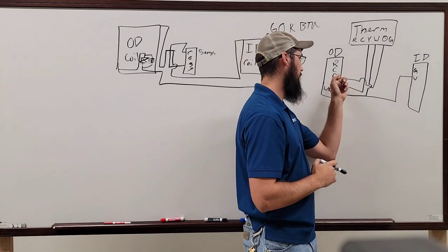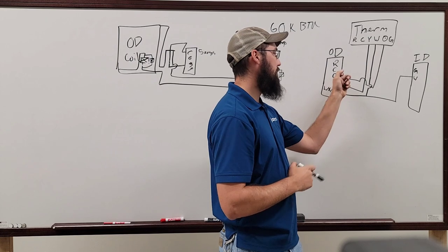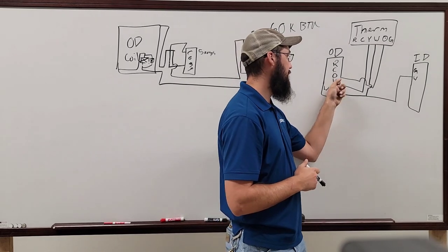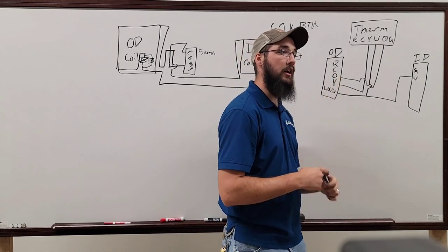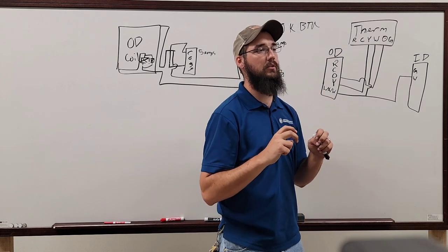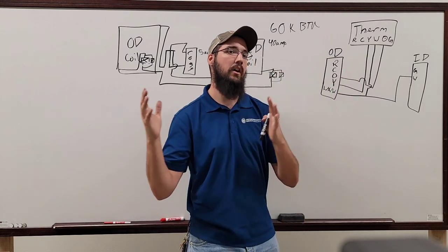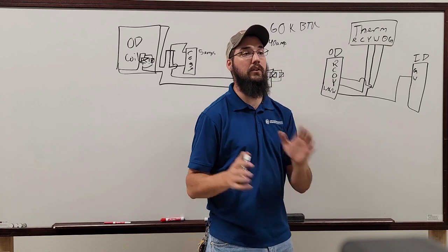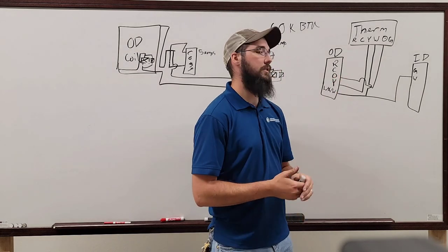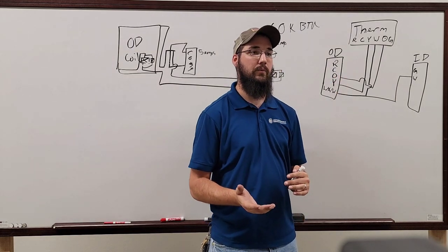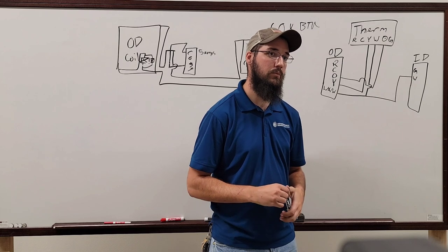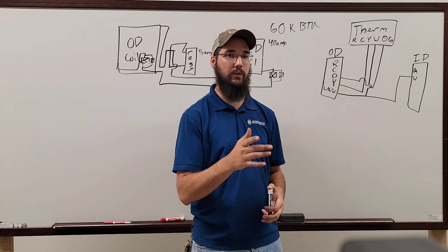Take the basic principle of what we're talking about. So everybody but Rheem, for the most part, will not energize O for heat. They will only energize Y. And Y becomes the outdoor coil signal, not the cooling signal. Like normally we're trying to think, okay, Y is your cooling signal. Actually, in the heat pump, it strictly means it's firing your outdoor coil. That's its function, is Y. So O decides, are we gonna be heating or cooling? What does it energize? The reversing valve. No, O energizes the reversing valve, thank you.